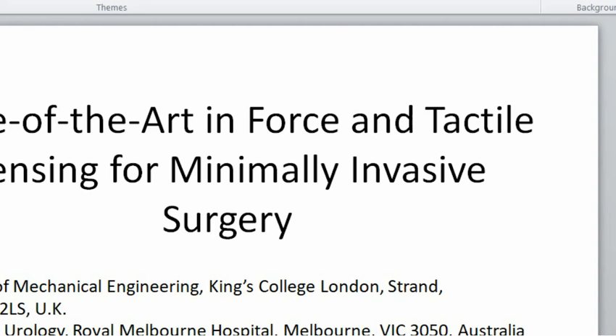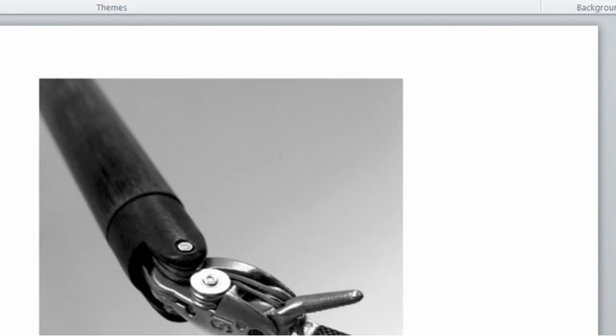Modern laparoscopic instruments such as EndoWrist instruments and da Vinci surgical systems have an articulated joint at the distal end of the shaft near the gripper, providing more degrees of dexterity to facilitate surgery. So, it was shown in the picture. However, because the EndoWrist and other commercial laparoscopic instruments possess no force sensing capability, the effectiveness is still limited.